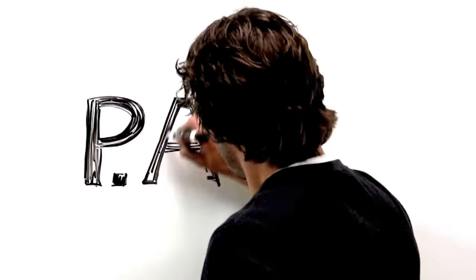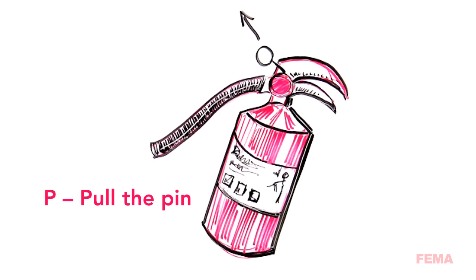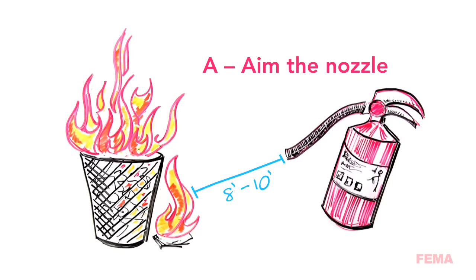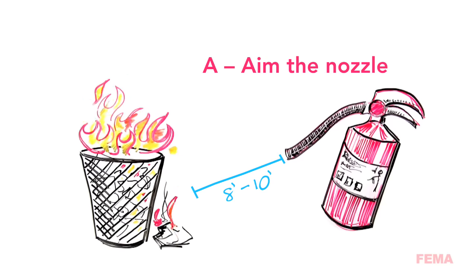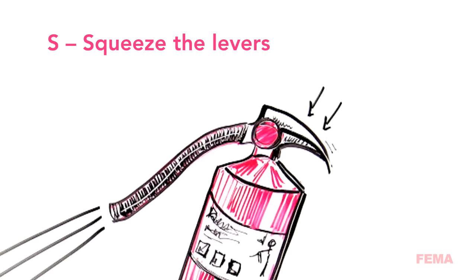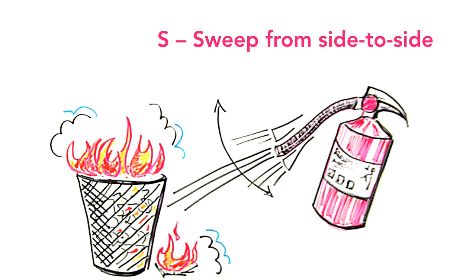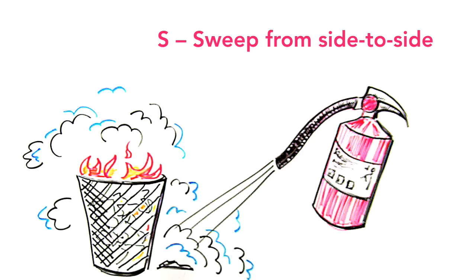Once you've determined that the extinguisher is the correct type for the hazard, proceed to operate the extinguisher using the PASS technique to control and extinguish the fire. First, hold the extinguisher upright and pull the pin. Next, stand 8 to 10 feet from the fire and aim the nozzle at the base of the fire. Do not get too close or aim the nozzle too high. Once the nozzle is aimed at the base of the fire, squeeze the levers together to begin discharge of the fire extinguishing agent. Maintain your distance from the fire and sweep the nozzle from side to side, sweeping 3 to 6 inches beyond the right and left edges of the fire. Discharge the extinguisher until contents are exhausted to prevent re-ignition.